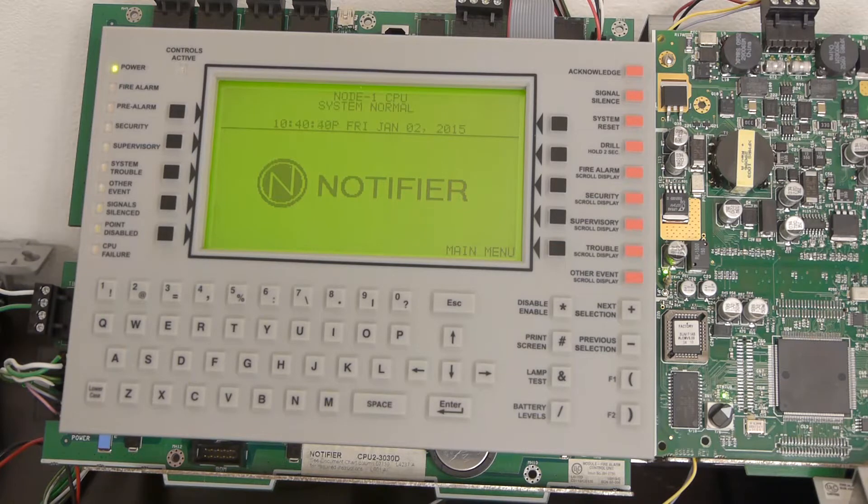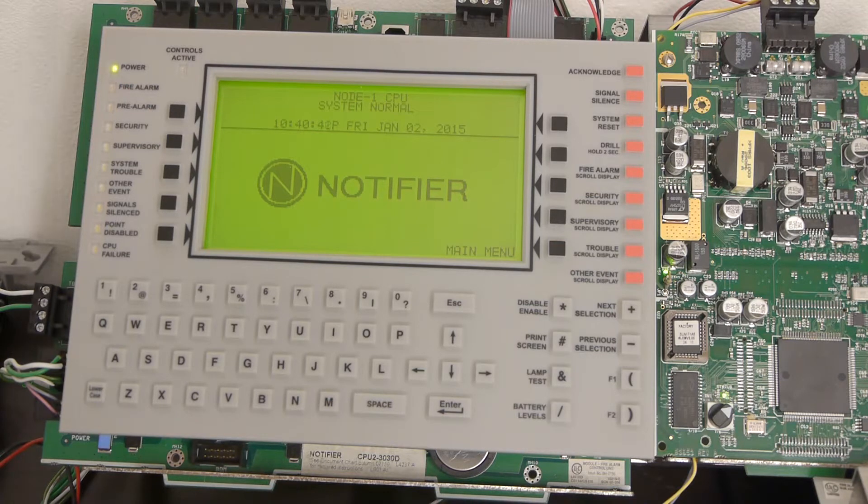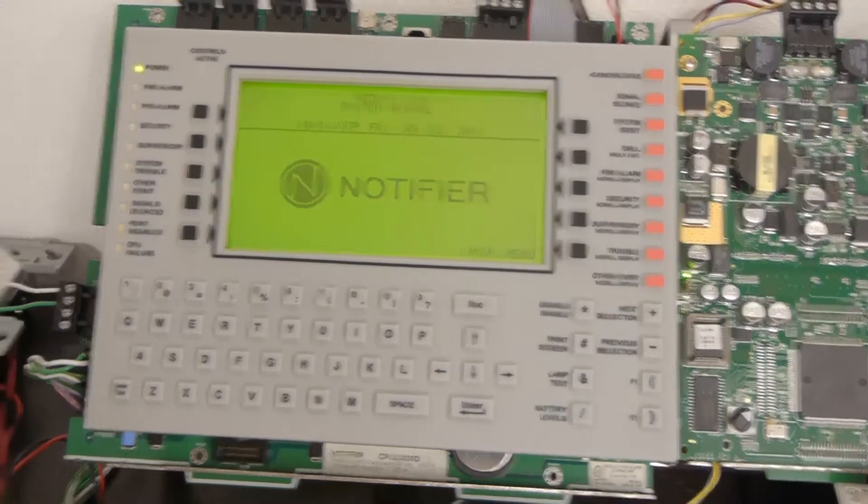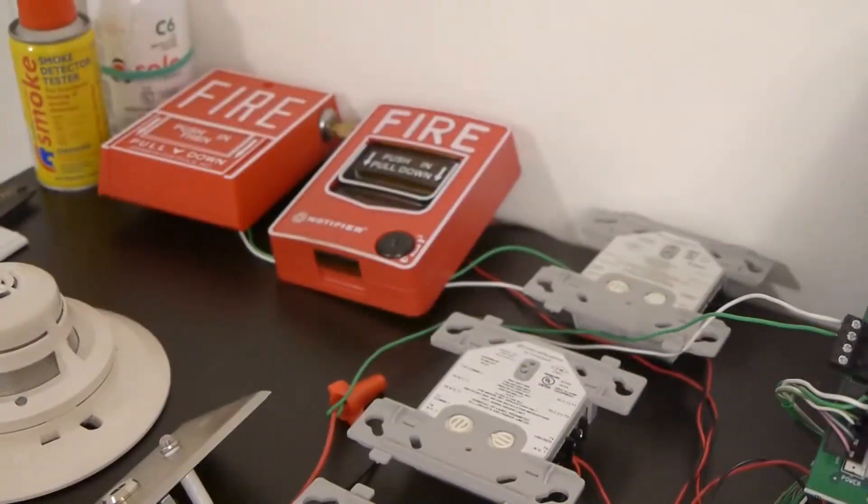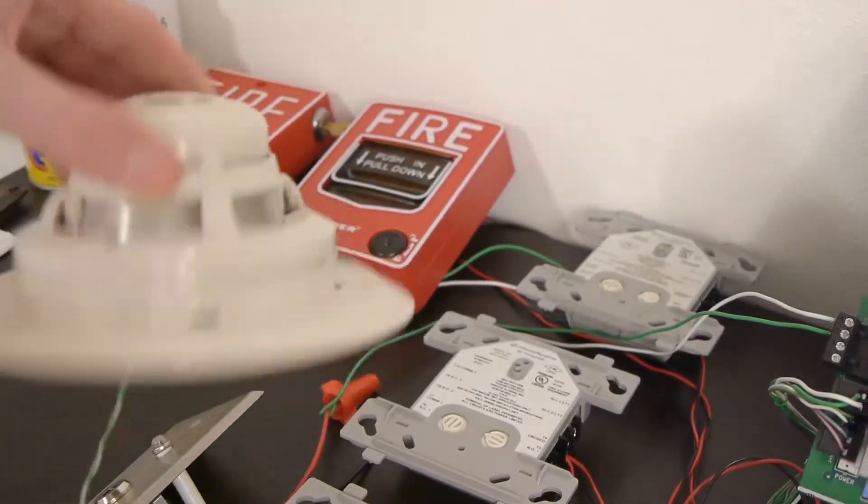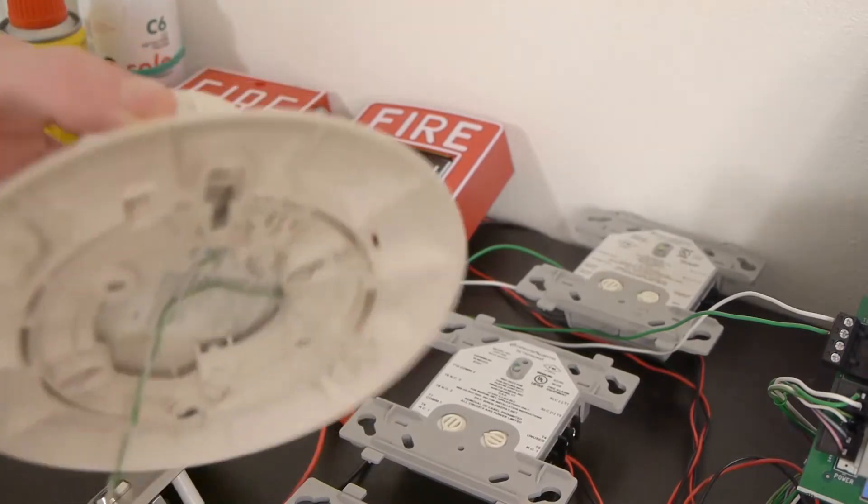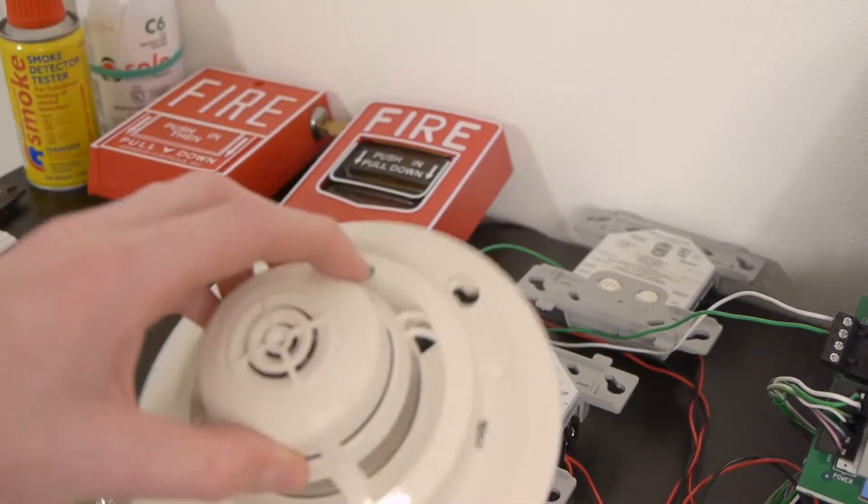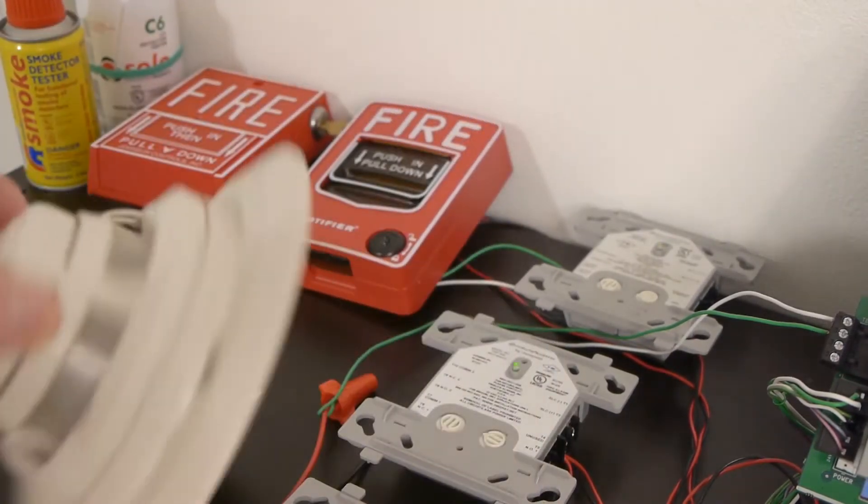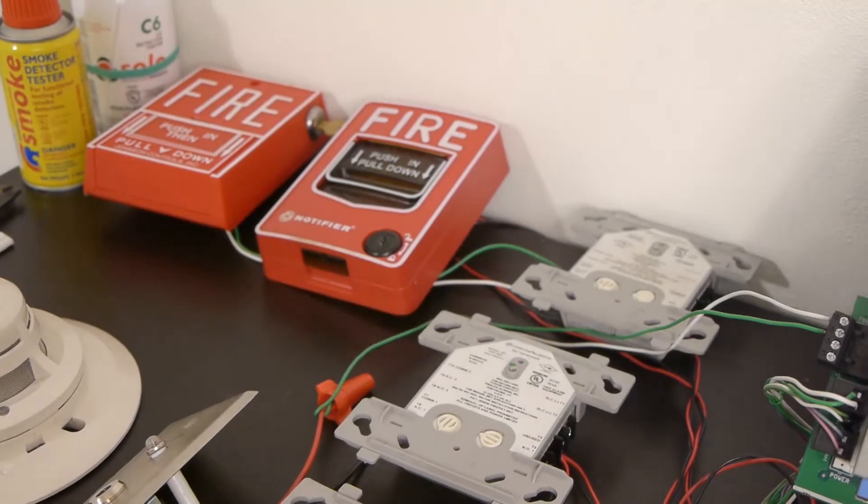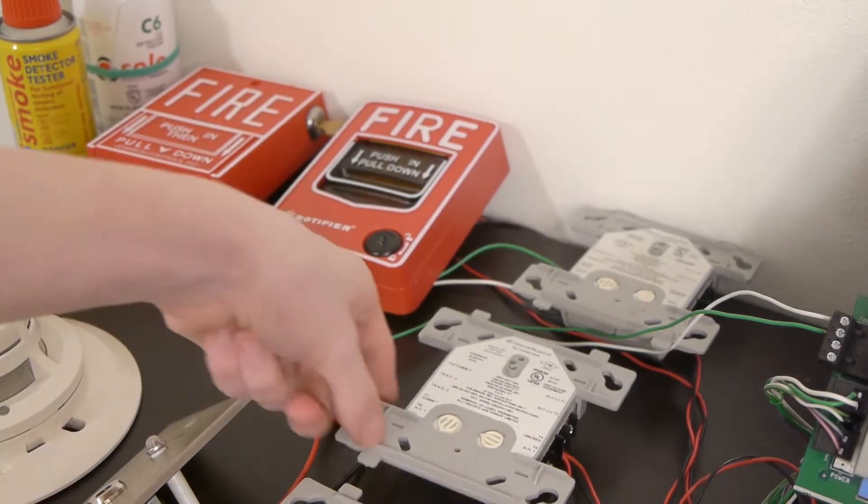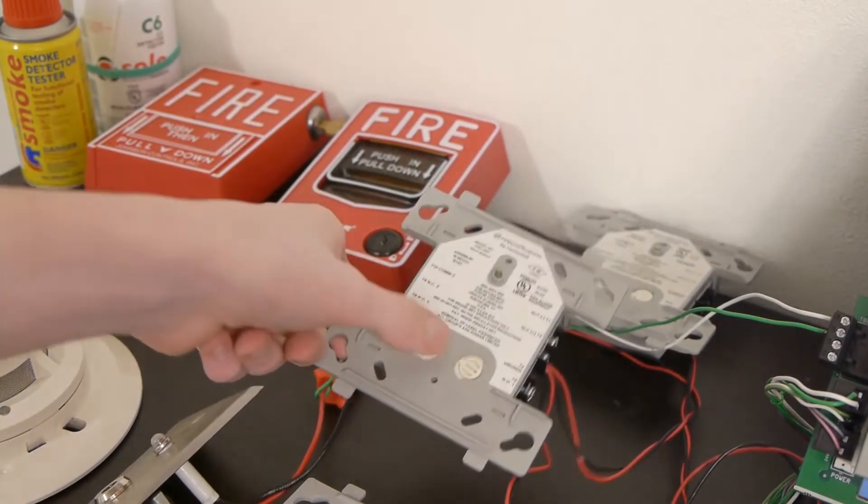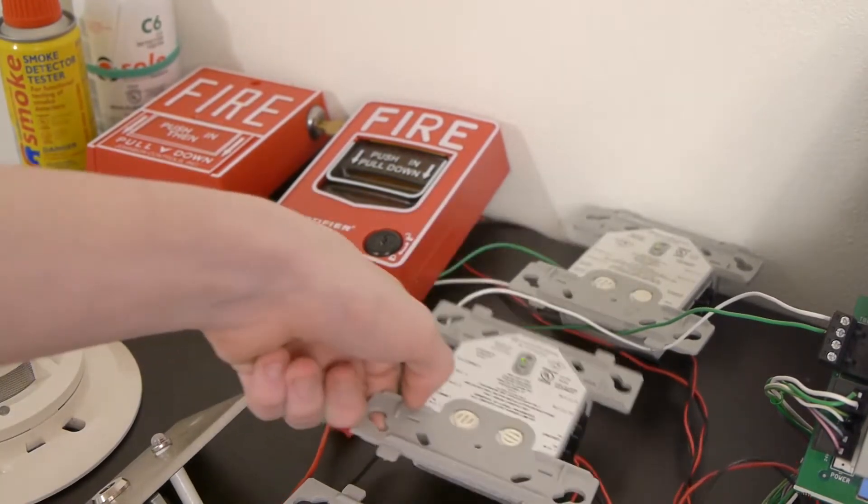The first thing we're going to do is figure out which device we're going to enable or disable. You should already know which device this is. If you know which detector head it is, you can take the detector head off the base and look on the back, or there should be a label on it somewhere that says what the address is. If it's a module, you can take the cover off and look at the dials.